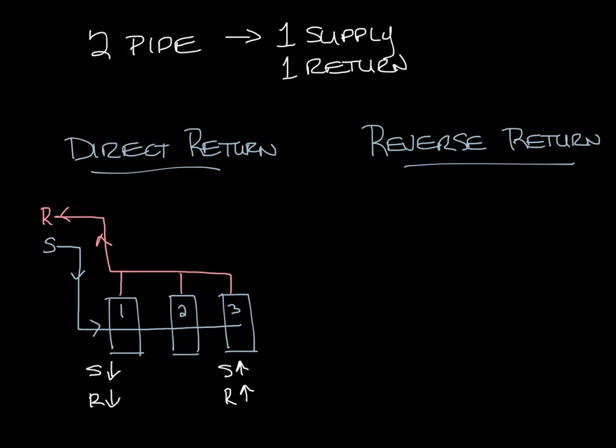So looking at this you can see that the loss going through the first unit through the supply and into the return is going to be the lowest. So during low flow conditions most of the water will want to go through the first unit.